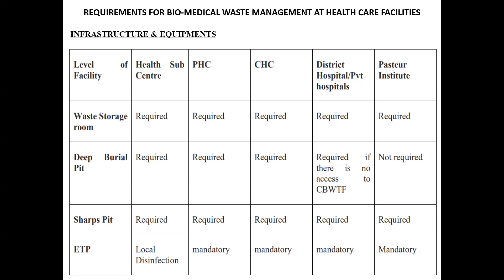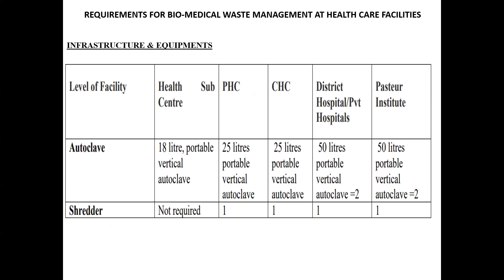Apart from that, the best for pre-treatment, if you could get, is the autoclave. If you have an autoclave, that means pre-treatment is sorted out. You don't have to do chemical disinfection. So it is more effective also because this is sterilization, whereas if you do it with chemicals like bleaching powder or hypochlorite solution, even though it's 1%, it's simply disinfection, not sterilization. So a shredder is also required, as you can see here, from PHC up to district level.